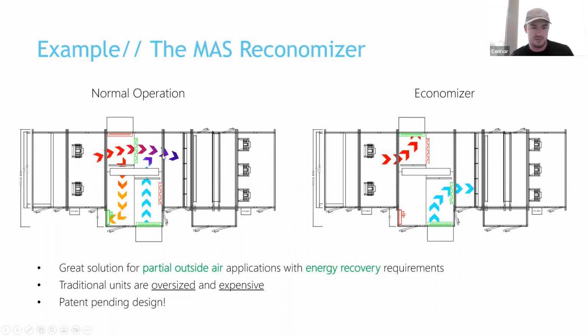On your left here, for our normal operation, you're bringing in your minimum outside air and you're exhausting your minimum exhaust air through that wheel. This is a wheel shown on the drawing. And when you go into an economizing mode, you bypass the wheel entirely and you save on footprint, you optimize the unit. This has been a great design for us, for Long, and for all of our reps.